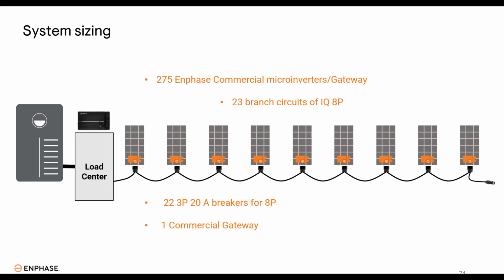So here's an example of what that might look like. We have a system with 275 commercial microinverters. That's 23 branch circuits of the IQ8P 3P microinverter. And we have one commercial gateway. That commercial gateway is going to be installed near our sub panel board load center, and that's going to be monitoring all of those microinverters. And then that sub panel is going to be taking all of that home run power, combining it right there, and sending it over to the point of interconnection.